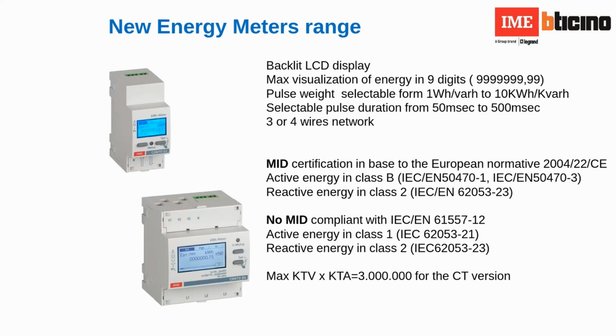Okay, speaking about MID version means that active energy parameter is compliant with the standard EN 50470 in class B. The non-MID version is in class 1, and according to the standard EN 62053. These two norms deal with the test condition of the energy meter. So the EN 50470 classifies active energy in class A, B, or C. The EN 62053 is classified in class 1 or 2.